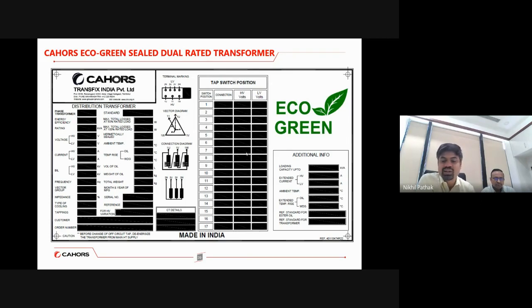So basically, a 2 MVA transformer, for example, with the base capacity here as a baseline, it can go up to either 2200 kVA with class A insulation or 2400 kVA. And this can be practically achieved and it can be adopted.